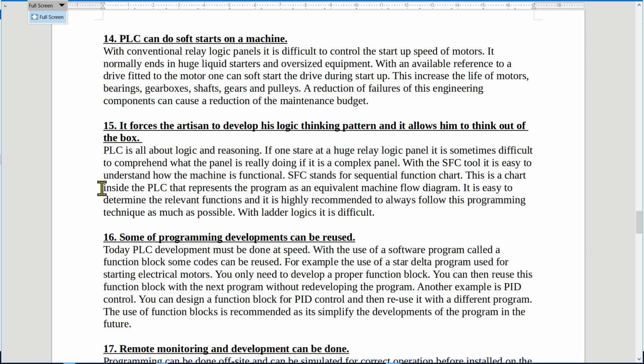Because even if you never worked with the machine, if there's SFC being used inside the PLC, you can actually understand what the machine is doing at certain times. And in our lives, this is very important, because if you get to a machine that is not operational, to understand how the machine is working is very, very difficult. I always say during my training sessions that the most important tool that you can have is to understand how the machine is operating. Even if you don't have PLC equipment, you can use the SFC concepts to draft the operation of the machine to assist in fault finding.